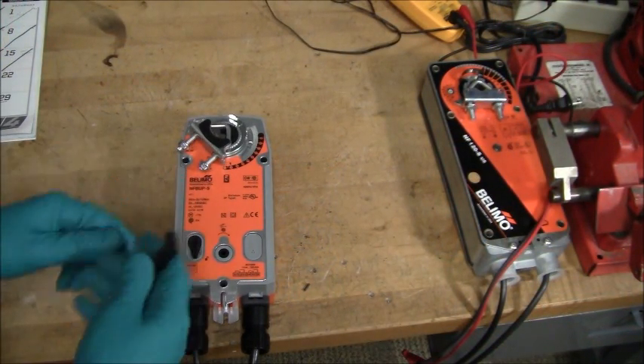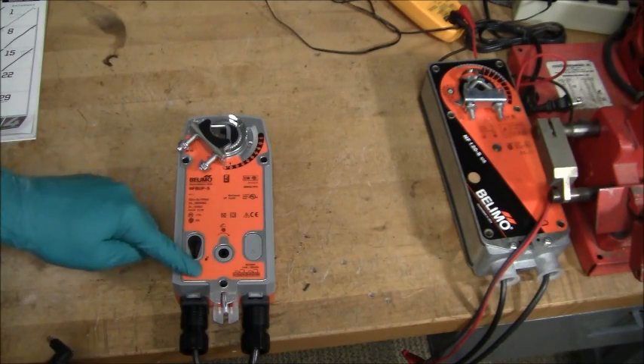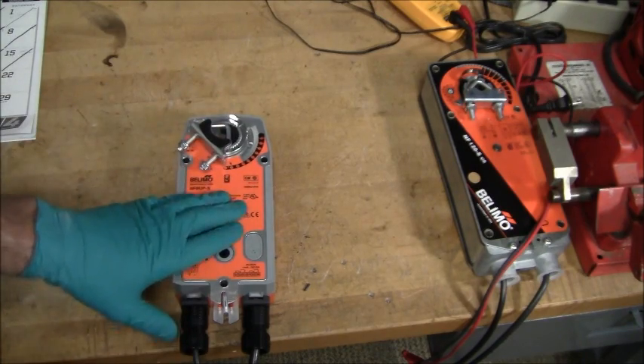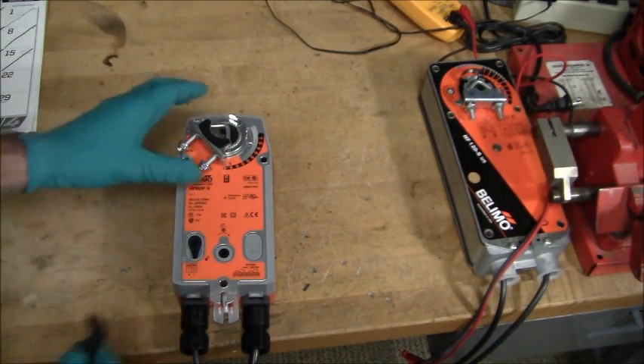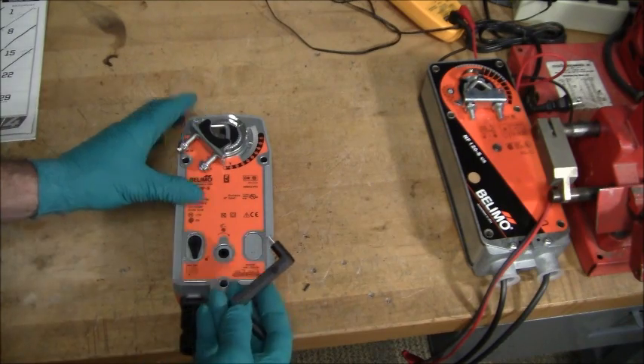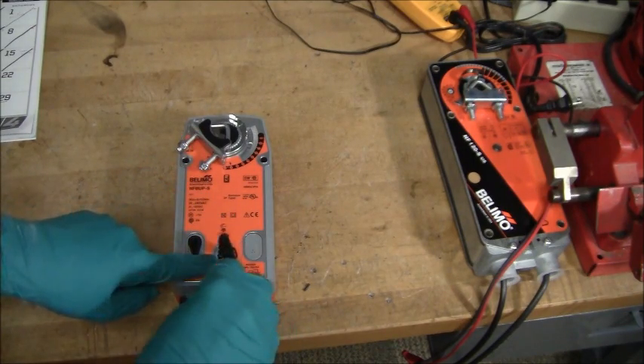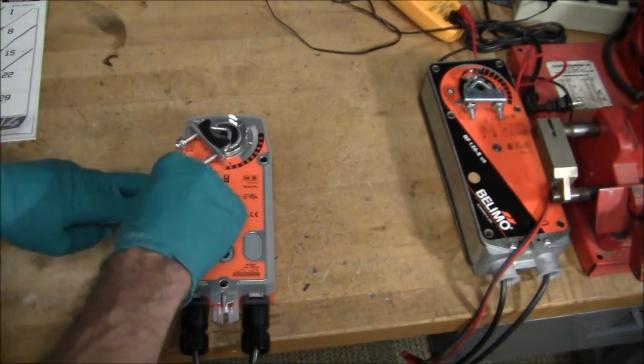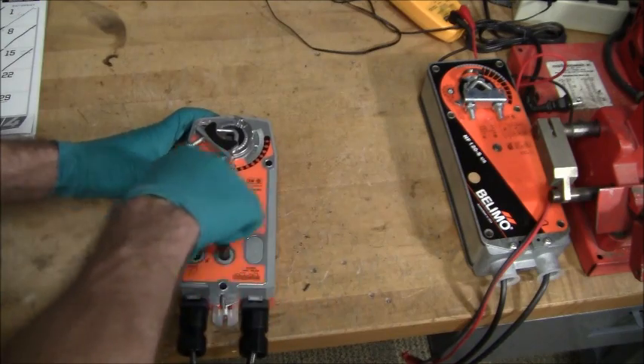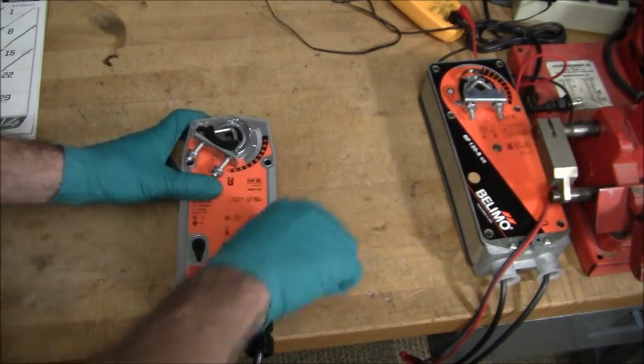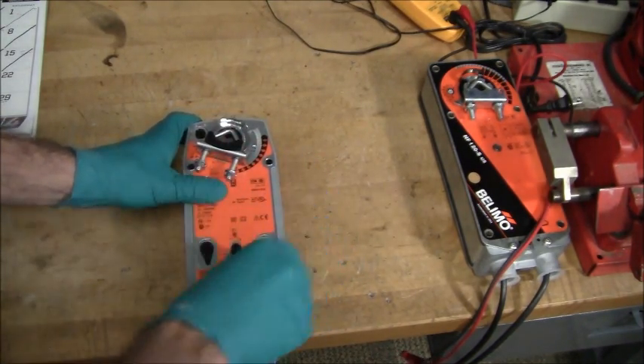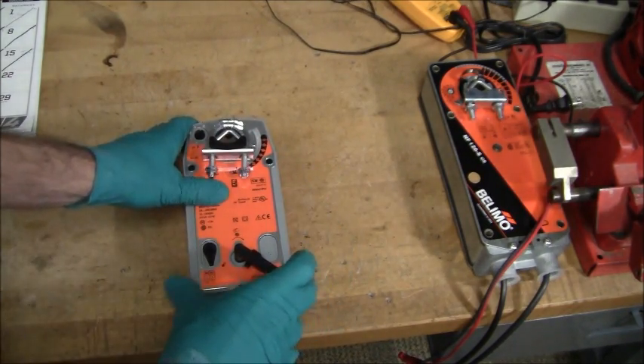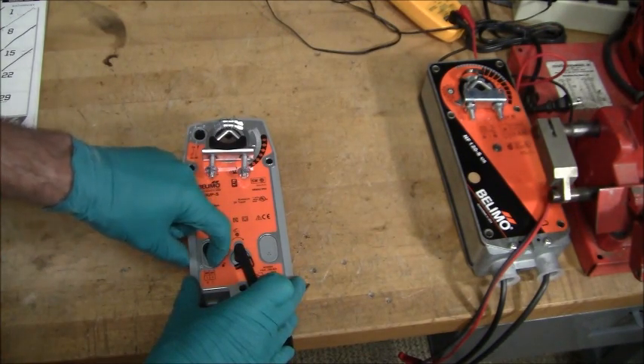Now what I'd like to do is explain what the lock and unlock feature is, and what this little handle does. If this new motor was to fail, you can take this little arm, put it inside here. It tells you what direction to turn in. If you watch the cam, you'll see that I'm actually manually opening that up. So if there was a damper attached, I could manually open it, set the damper to whatever I want. Then you take this lock and move it to lock. You can pull this out, and now that's going to lock in exactly where you set it at.